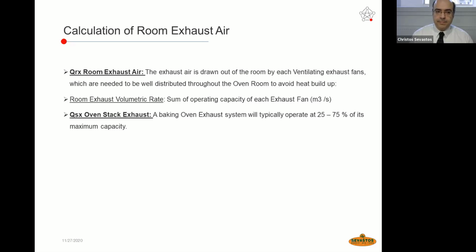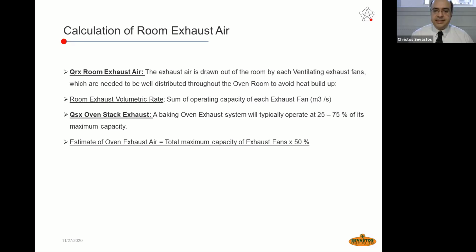The other factor of the mass balance equation is the QSX, the oven stack exhaust. A baking oven exhaust system will typically operate at 25 to 75% of its maximum capacity. So the estimate of oven exhaust air is the total maximum capacity of the exhaust fans, which is given by the supplier, the manufacturer of the oven, multiplied by 50%. This is half of the maximum capacity of the exhaust fans.